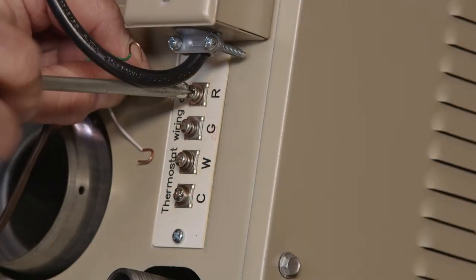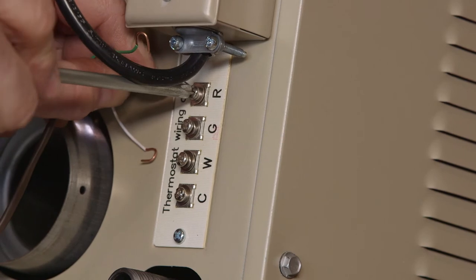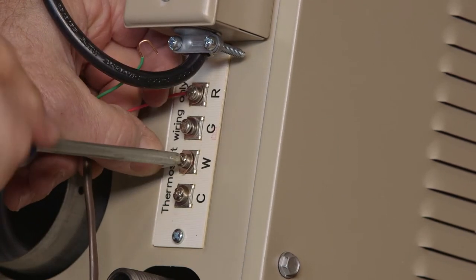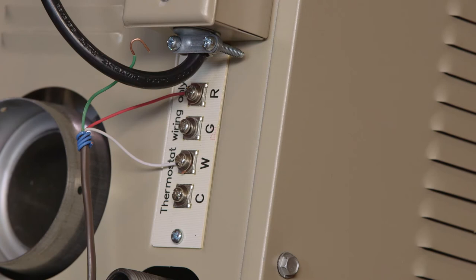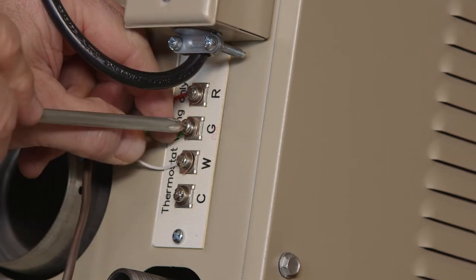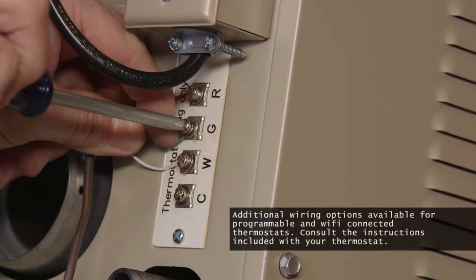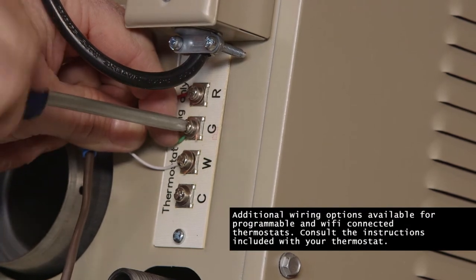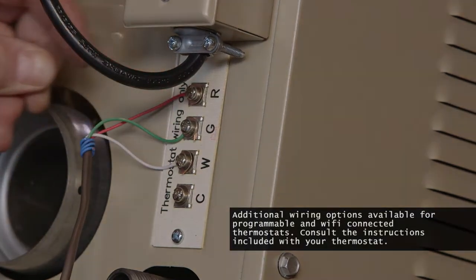Below the junction box is a terminal strip with 4-screw terminals for the remote thermostat connection. Only the terminals marked R and W are needed for the thermostat. If your thermostat has a manual automatic fan switch setting, attach a third wire to the optional G-terminal.